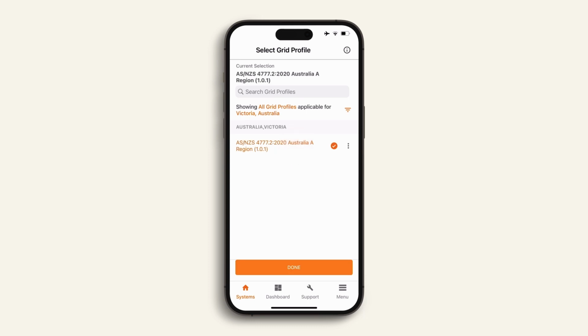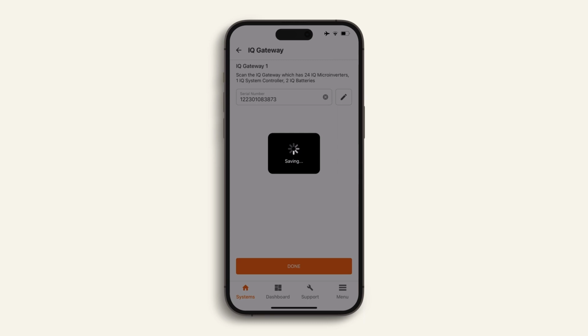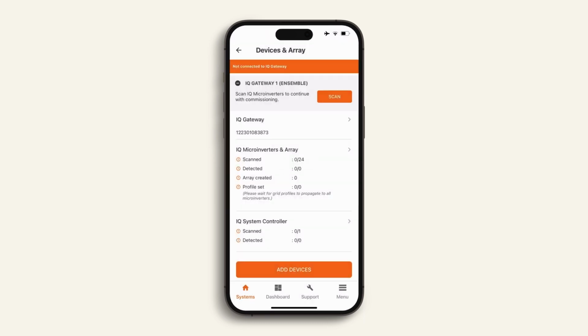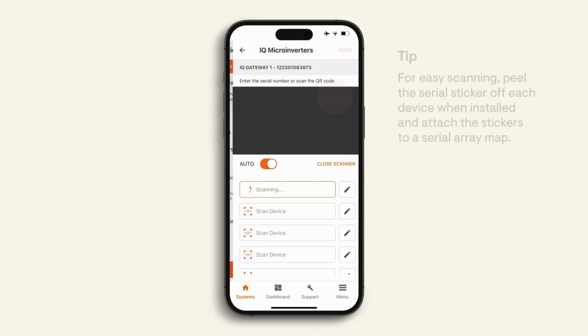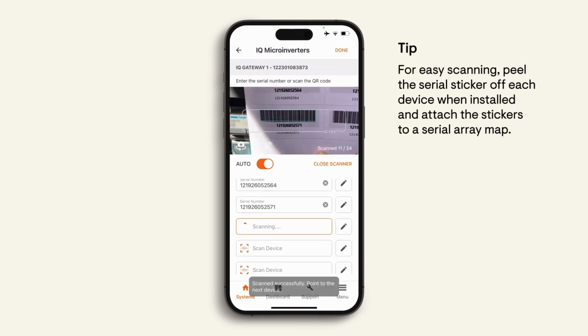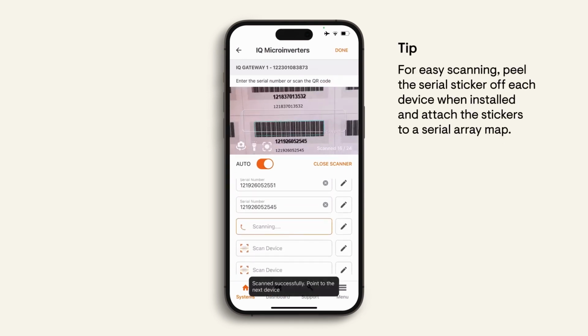Once you've scanned the IQ Gateway serial number, select the grid profile for the site location, and then scan the remaining devices. A simple way to do this for each of the microinverters for the solar PV arrays is to use the serial number stickers on the array map.